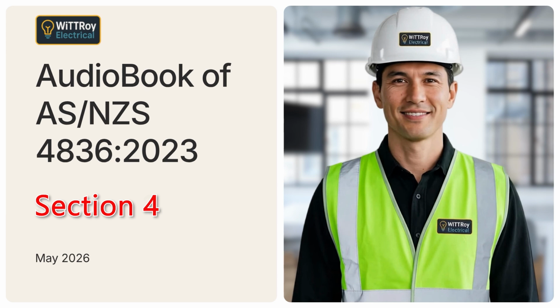Battery terminals must remain protected by insulating covers where practicable while electrical work is being carried out on or near them. DC systems and batteries can deliver very high fault current. Short-circuiting battery terminals or DC conductive parts can create large arcs. Those arcs can cause personal injury, arc flash events, ignition of hazardous gases, ignition of other material, or fire. So batteries must not be treated as low risk just because the voltage may look low. A low voltage battery system can still release very high current.